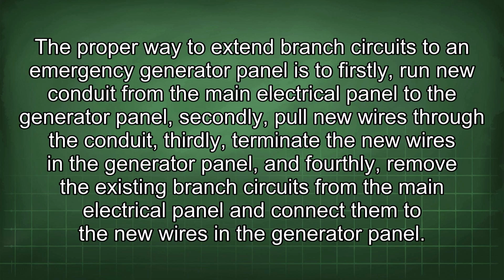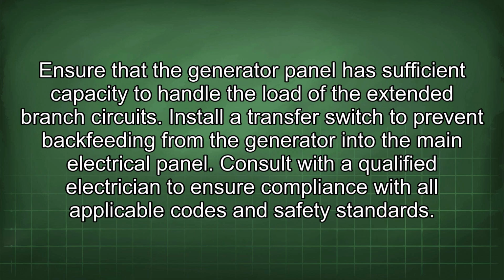The proper way to extend branch circuits to an emergency generator panel is to, firstly, run new conduit from the main electrical panel to the generator panel. Secondly, pull new wires through the conduit. Thirdly, terminate the new wires in the generator panel. And fourthly, remove the existing branch circuits from the main electrical panel and connect them to the new wires in the generator panel. Ensure that the generator panel has sufficient capacity to handle the load of the extended branch circuits.